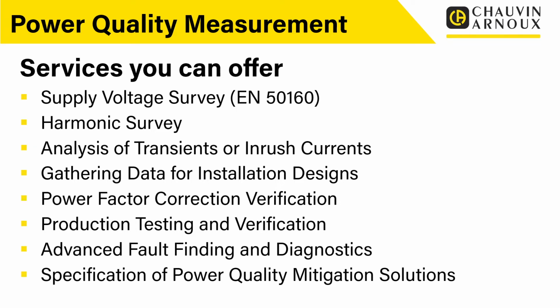Next one down, gathering data for installation designs. We talked about pre-installation surveys. This is very similar to that, but this is looking in a bit more detail, obviously, from your power quality point of view. So what we can do is go in and gather the characteristics of the installation. We know the voltage tolerances, we know the frequency tolerances. We know what's there already, so we know what the existing power factor is. So if we're going to add equipment, what's that going to do to the power factor? Are we adding equipment that's capacitive, in which case it'll move it a certain way? Are we adding more inductive equipment, in which case it's going to go the other way? So by gathering the data in advance, we can provide that to the designer, and then the designer can carry out the design or manufacture a piece of equipment or whatever. You can gather that data and provide it to them as a service, and that means the design will be fit for purpose and everything will go straightforward, rather than just installing something and then finding out afterwards all the impact it's got.